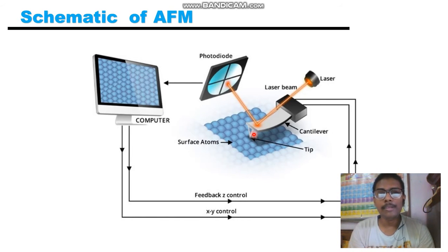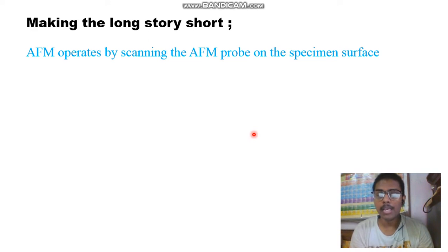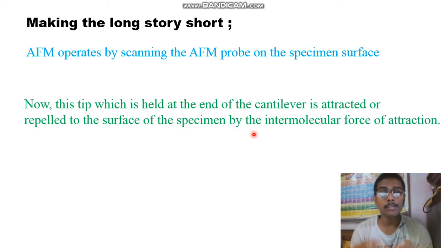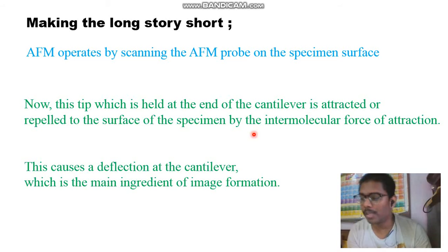AFM works based on a three-stage mechanism. First, the AFM probe moves on the specimen surface. Then, the tip held at the end of the cantilever is attracted or repelled to the surface of the specimen by the intermolecular force of attraction — which can be attraction as well as repulsion. This causes a deflection in the cantilever, which is the main ingredient of image formation.